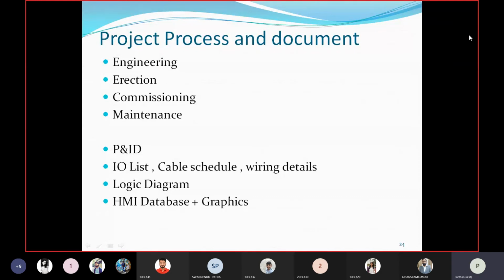First engineering will be done, then erection, meaning installation of instruments and devices, then commissioning, meaning all the cables are connected. After that, loop check, meaning continuity check of the cable, will be done, and then all the parameters will be verified and all the logic will be checked with OEM, operation and control, and system engineer.